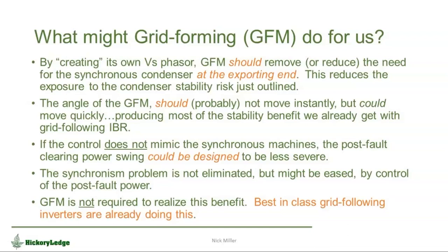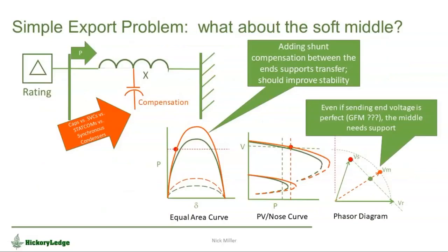then I don't need the condenser, but I need to tell the grid forming inverter to chase the receiving end system. Otherwise, I end up back with the same problem I had with the synchronous machine, which was that it was unstable. So the grid-forming inverter does not want to look like a synchronous machine, otherwise I have to back the power transfer. But it wants to maintain voltage and it wants to chase. So somewhere it needs to be better than the grid-following inverter and better than the synchronous machine. And we've got a little work to do with that.